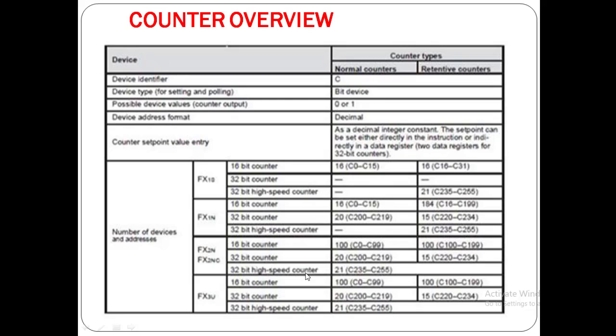In FX3U, 16-bit counters are 100 from C0 to C99, and retentive counters are also 100 from C100 to C199. 32-bit counters are 20 from C200 to C219. Retentive 32-bit counters are 15 from C220 to C234. 32-bit high-speed counters in normal condition are 21, which are C235 to C255.